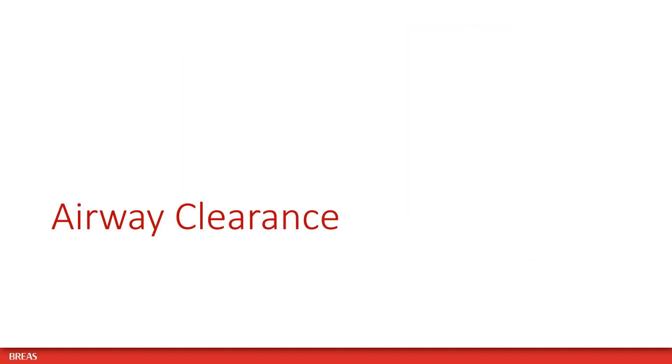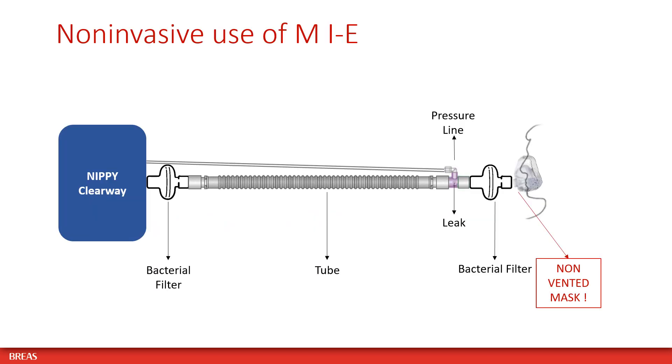Please adhere to the following recommendations when providing airway clearance with mechanical insufflation-exsufflation to your patient. For the non-invasive use of mechanical insufflation-exsufflation, we recommend placing a bacterial filter at the air outlet of the device, as well as a bacterial filter in between the leak adapter and the mask.